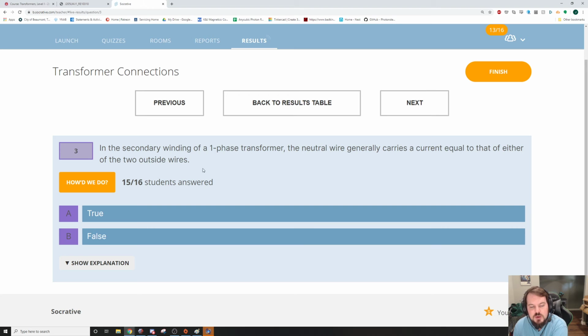In the secondary winding of a single-phase transformer, the neutral wire generally carries a current equal to that of either of the 2 outside wires. So the neutral wire carries the difference of the 2. It carries the unbalanced load in a single phase.